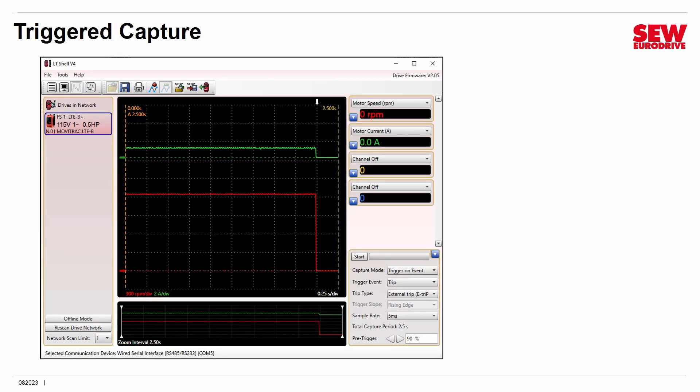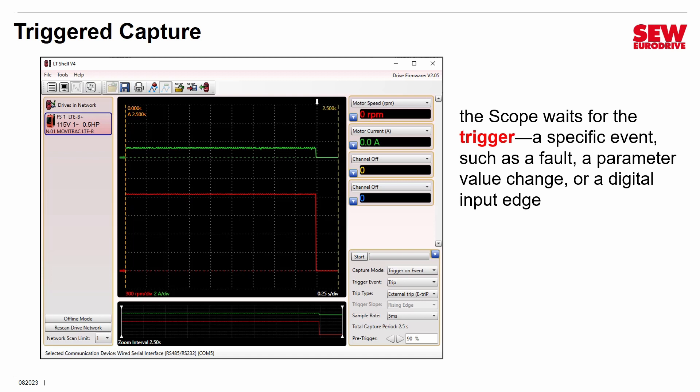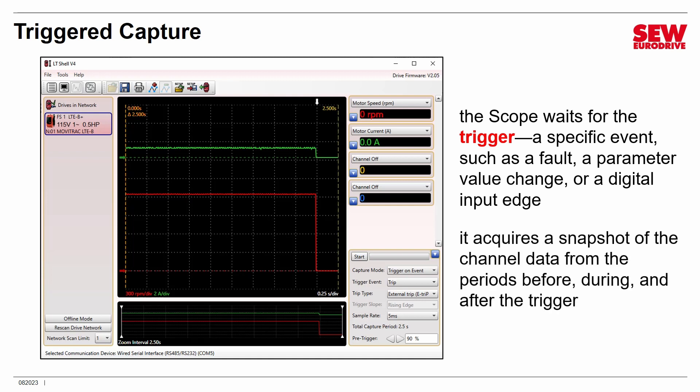Let's talk about triggered capture. The big idea: when you're in this mode, the scope is waiting for the trigger — a specific event. It could be a fault occurring, any fault or a specific fault. It could be a parameter changing to some value. Or it could be one of the digital inputs rising or falling, generating an edge. Whatever the trigger is, the scope is watching for it, and you pick what you want the trigger to be. When that trigger occurs, the scope acquires a snapshot of the channel data from whatever channels you've selected for the periods before, during, and after the trigger — giving you a picture of all the events surrounding it.